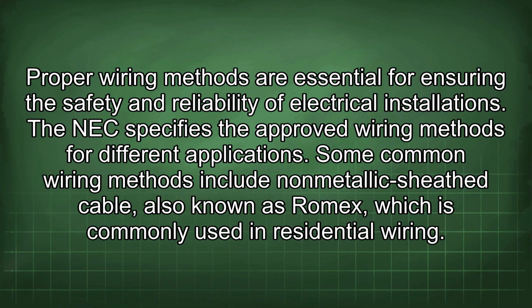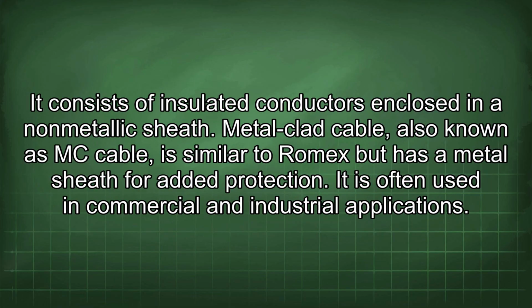Proper wiring methods are essential for ensuring the safety and reliability of electrical installations. The NEC specifies the approved wiring methods for different applications. Some common wiring methods include non-metallic sheathed cable, also known as Romex, which is commonly used in residential wiring. It consists of insulated conductors enclosed in a non-metallic sheath. Metal-clad cable, also known as MC cable, is similar to Romex but has a metal sheath for added protection. It is often used in commercial and industrial applications.